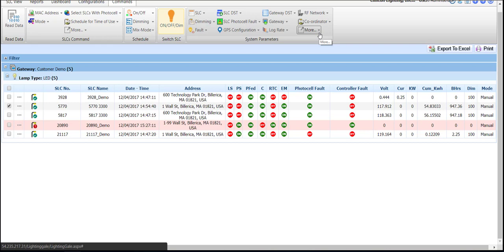But if you're not in front of the fixture, please remember that the status screen of the SLC will not update in real time. You will need to read data from that SLC — the so-called pull method — for the interface to display the controller's new state.